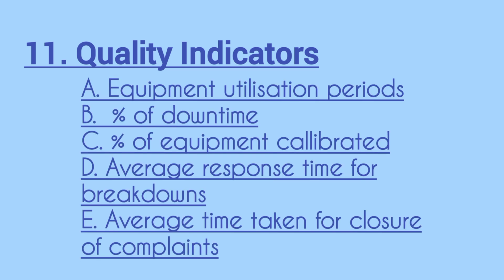Next is quality indicators. The quality indicators to be maintained are equipment-wise utilization time, specifically for high value equipment like CT, MRI, cath lab. Then percentage downtime or uptime equipment-wise for high value equipment. Then percentage of equipment calibrated as per the schedule. Average response time for complaints or service requests. And last is average completion time for closure of a complaint.